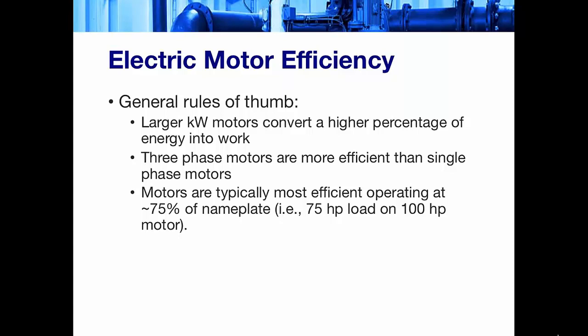And motors are typically most efficient operating at about 75% of the nameplate rating. So this would be a 75 horsepower load on a 100 horsepower motor. That would get you in the sweet spot for electrical efficiency.